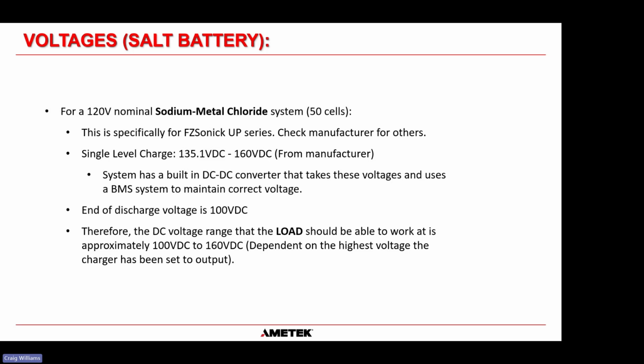And then for the salt battery, or the sodium metal chloride system, there are usually 50 cells inside these modules. This is specific to the Horion or the FC Sonic UP series. Always check other manufacturers for their details. Their single level charge can be anywhere between 135 volts and 160 volts, because Horion have a DC to DC converter built into their battery. So what they're saying is your battery charger can supply anywhere between 135 volts and 160 volts. It doesn't care, because what that DC to DC converter does is change that voltage into whatever the sodium metal chloride cells inside the battery module need.